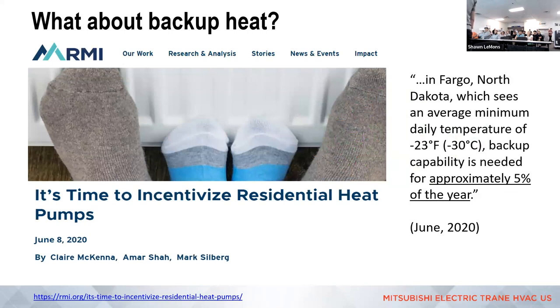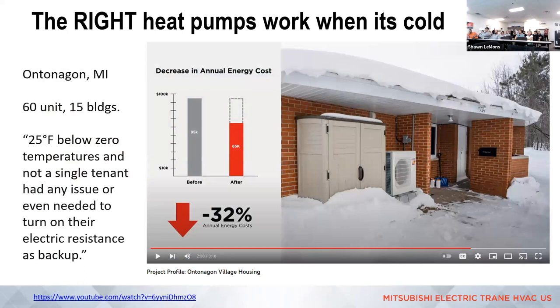Fargo, North Dakota, average minimum daily temperature of negative 23. Backup capacity is needed approximately 5% of the year, but you don't need that much of it. For our systems, it doesn't have to be the entire load of the house, so that's probably one piece that's unique. For us, backup is additive, on top of what the heat pump can already do. If these units can operate at 60% at negative 25, you only have to make up that difference, you don't have to add the entire backup. It's pretty important to think about. There's a fun video out of Ontonagon, Michigan, 60 units, 15 buildings, 25 below zero, and without backup. Pretty impressive stuff.